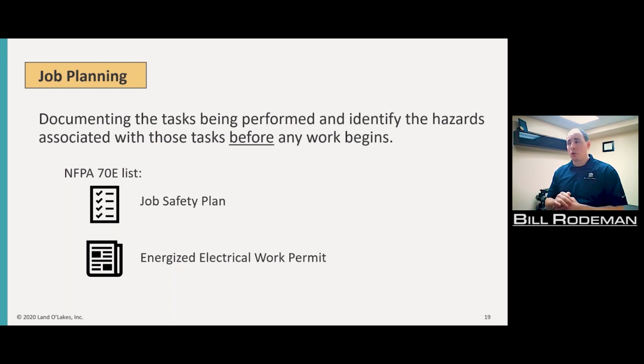The energized electrical work permit is really for performing repair work or making physical changes to energized equipment. An example I like to give is if I find that a contactor inside a piece of equipment is bad and needs replaced. If I'm going to leave power on to that contactor, which I don't know why you would, to pull it out and put a new one in, you have to have an energized work permit. That's going to cover justification for why you're not going to turn it off, your shock and arc flash risk assessment, other safety related work practices you're going to follow, and also approvals from others because you're doing that repair work or physical changes while the power's on the equipment.